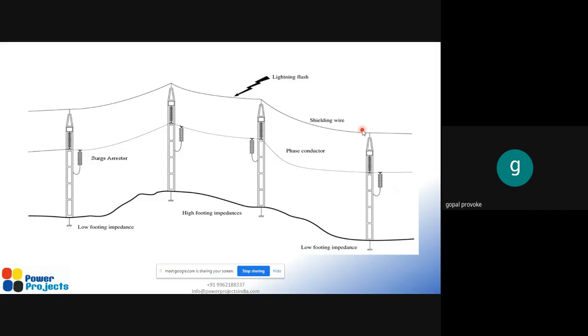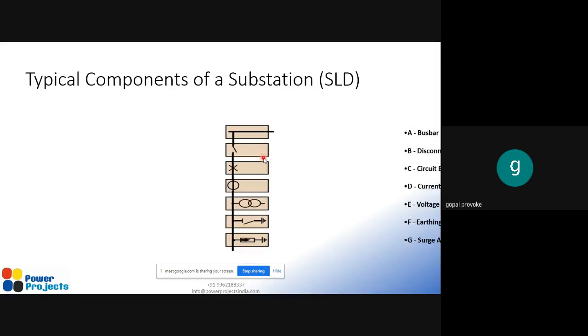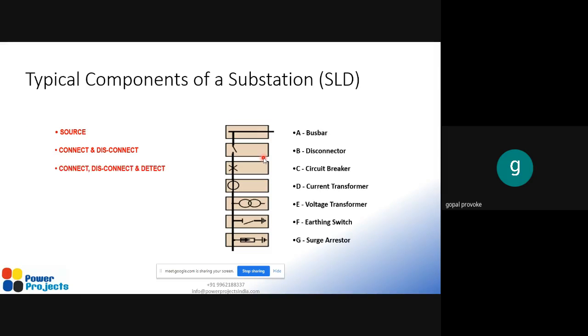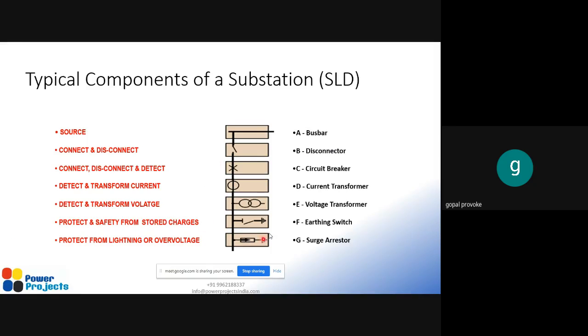This line does not carry any power. Only the phase conductors carry the power. Whenever there is lightning, it will receive the lightning and bypass it to the ground. The healthy phase conductors in the middle will not be affected. So again, I'm coming back to this SLD. These are all the equipment we have seen now: the bus bar, disconnector, circuit breaker, current transformer, voltage transformer, earthing switch, and surge arrestor.